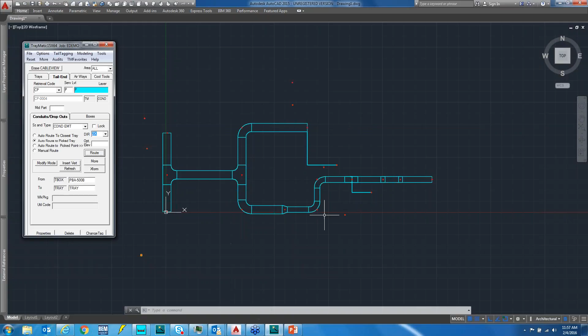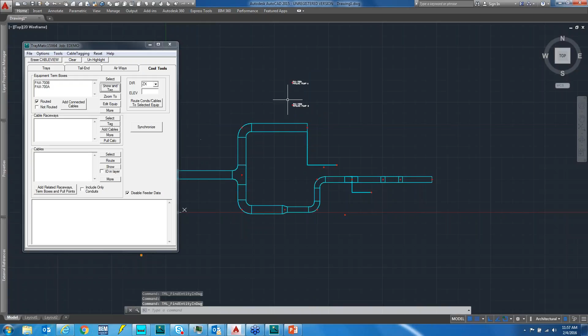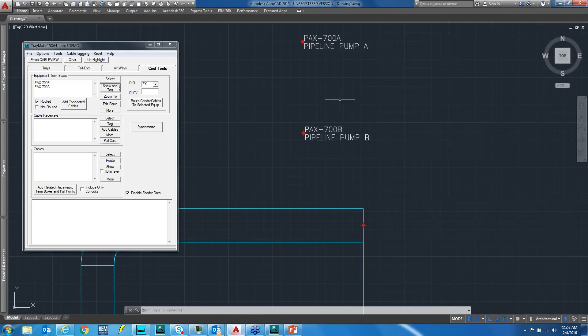So I'm going to go over to Cool Tools and select these two pieces of equipment. It tells me that's PAX 700A and B, so I'm going to show and tag those. The program will give me the equipment tag and description as it's reading it from the database, which is very handy. So I'll go back to my tail ends and again auto route my conduit.